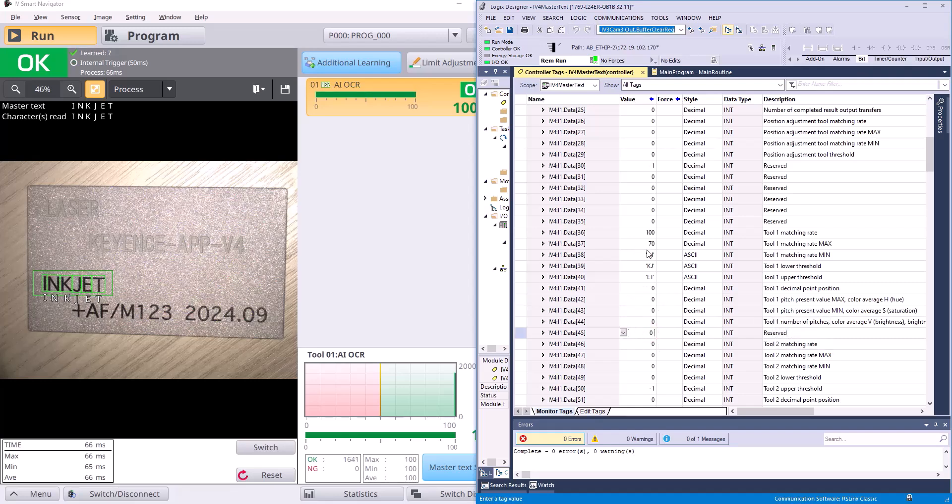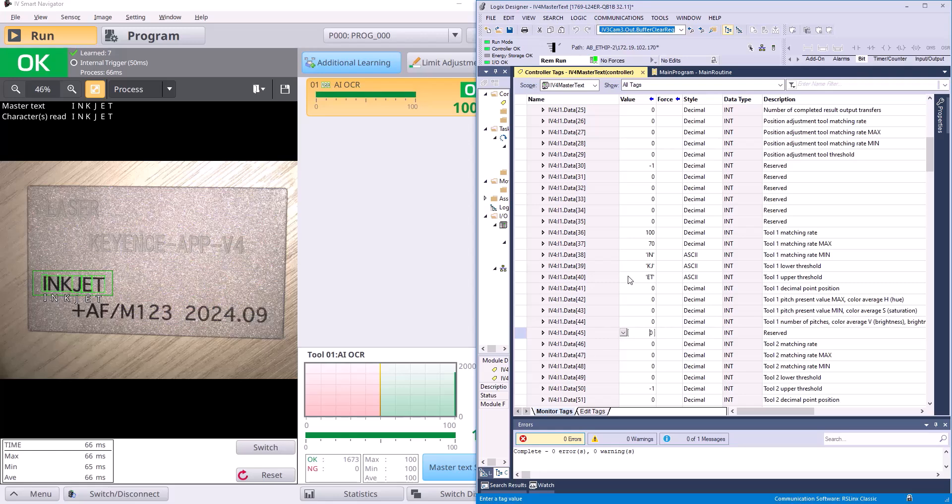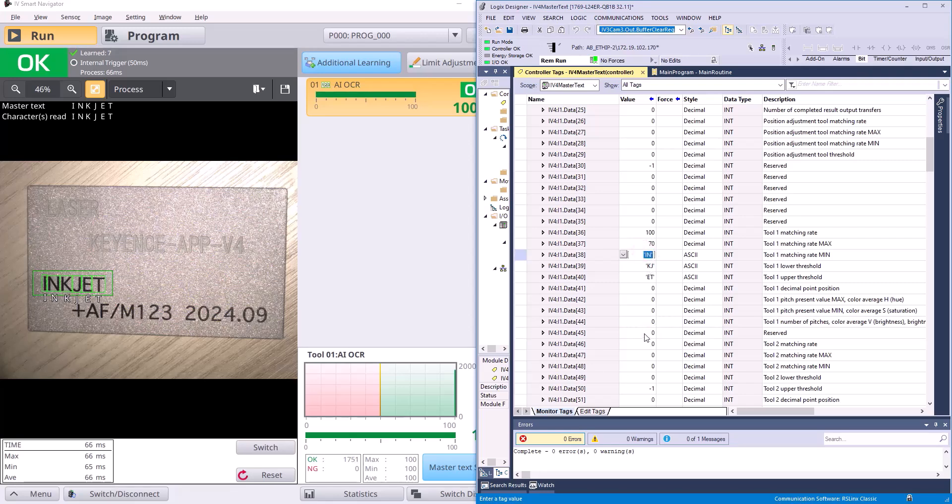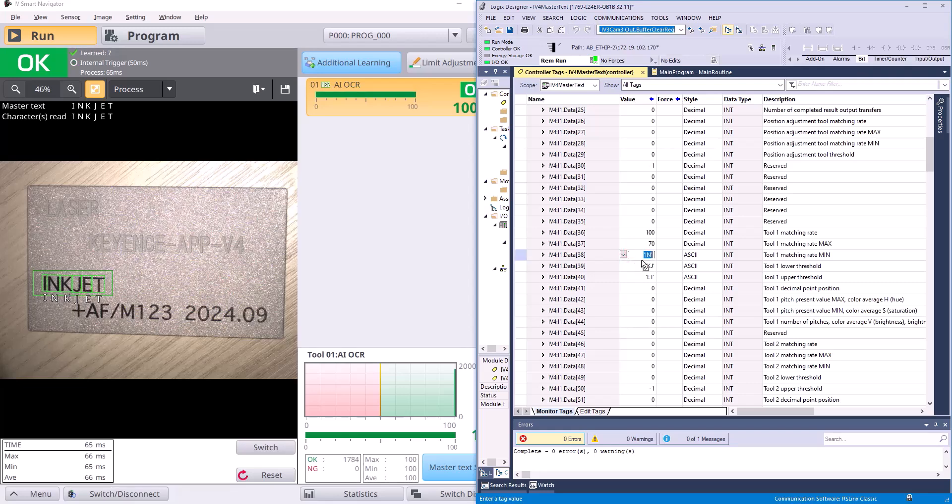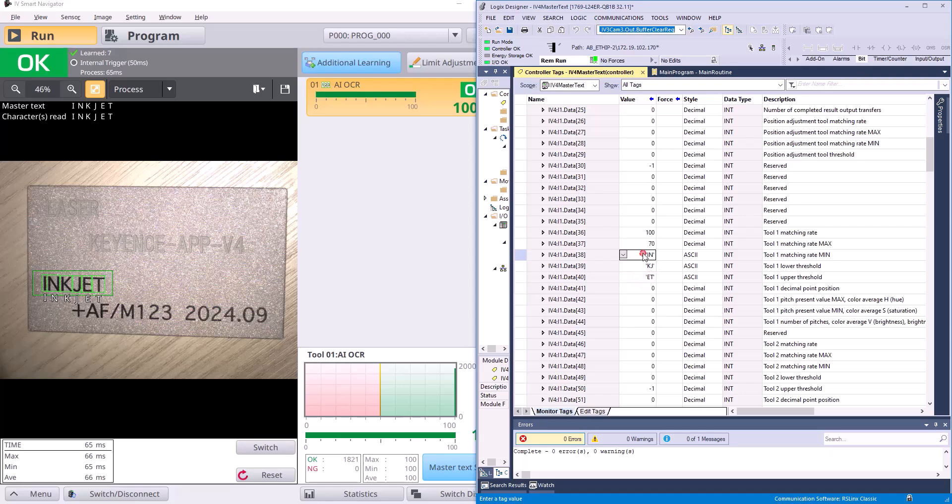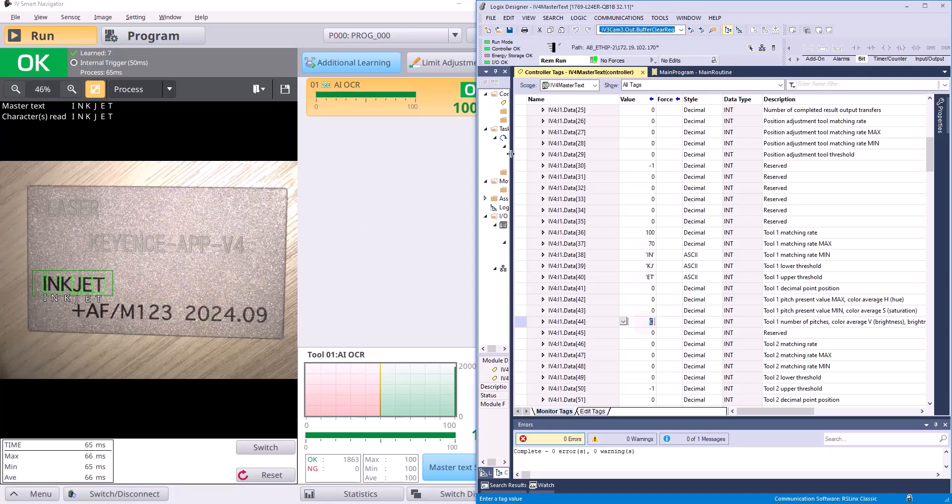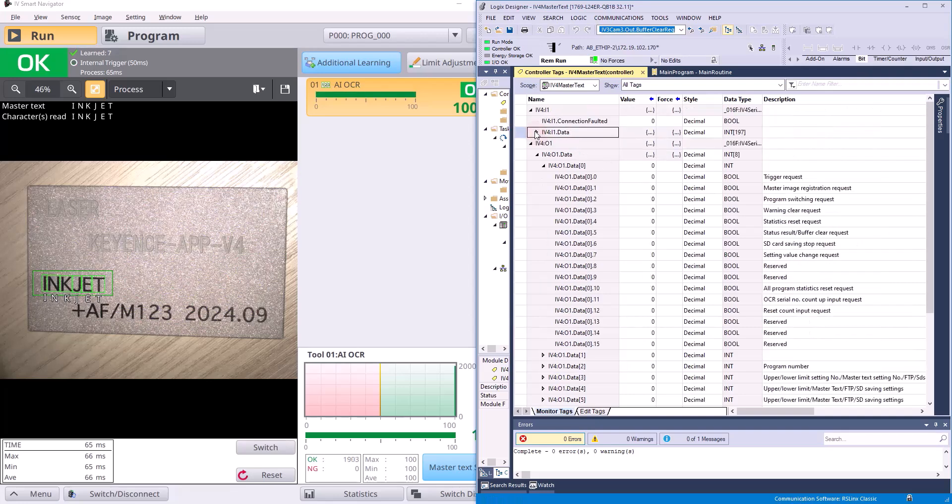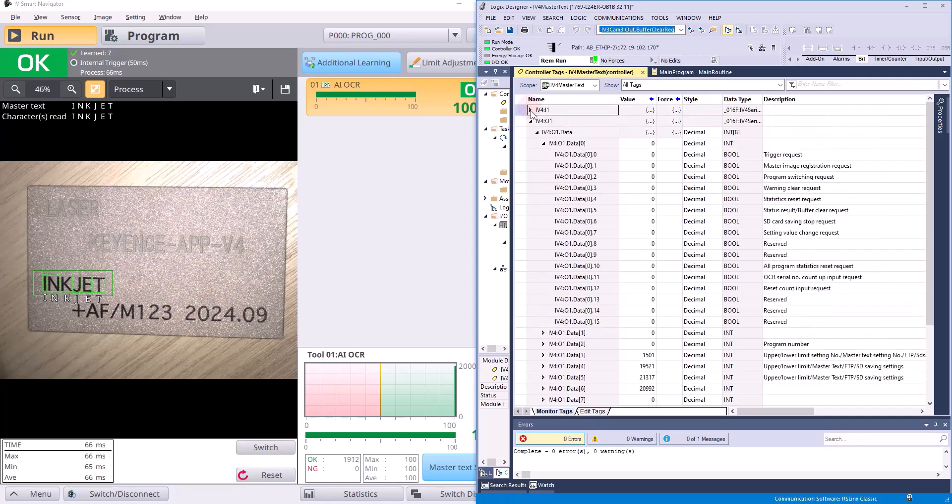These word areas from 41 to 45 all are reserved for when the tool is an OCR tool. You can read up to 16 characters just in the standard mode. If you do need to read in more than 16 characters, you'll want to use a different configuration of the EDS file, which we'll get into in a later video. In most cases you don't need to read more than 16 characters per tool. You can see if we were reading a longer string of text, those would all come in here.